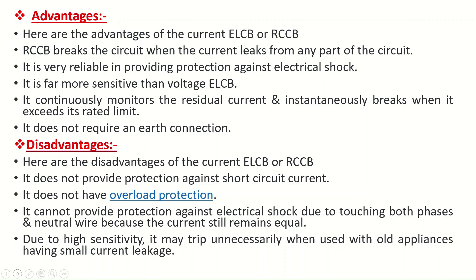Disadvantages of Current ELCB or RCCB: It does not provide protection against short-circuit current. It does not have overload protection. It cannot provide protection against electrical shock due to touching both phase and neutral wire simultaneously, because the current still remains equal. Due to high sensitivity, it may trip unnecessarily when used with old appliances having small current leakage.